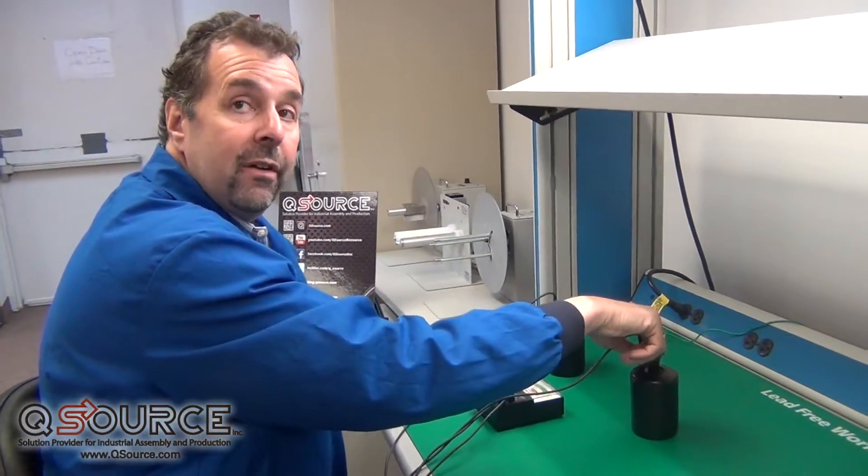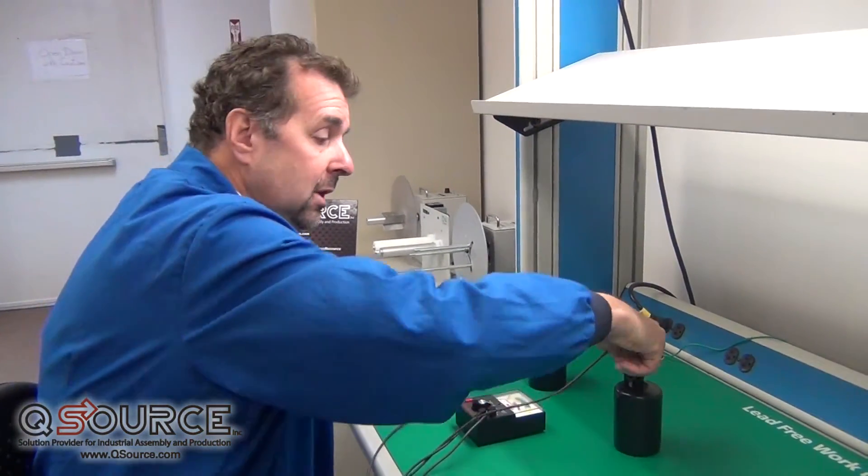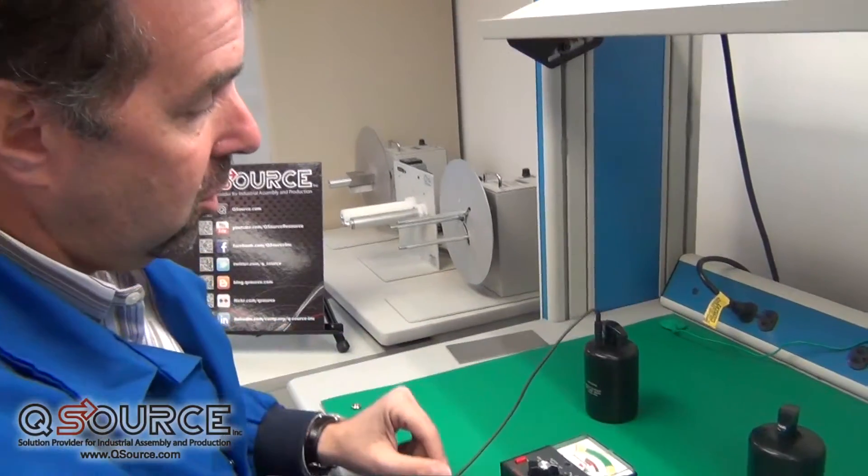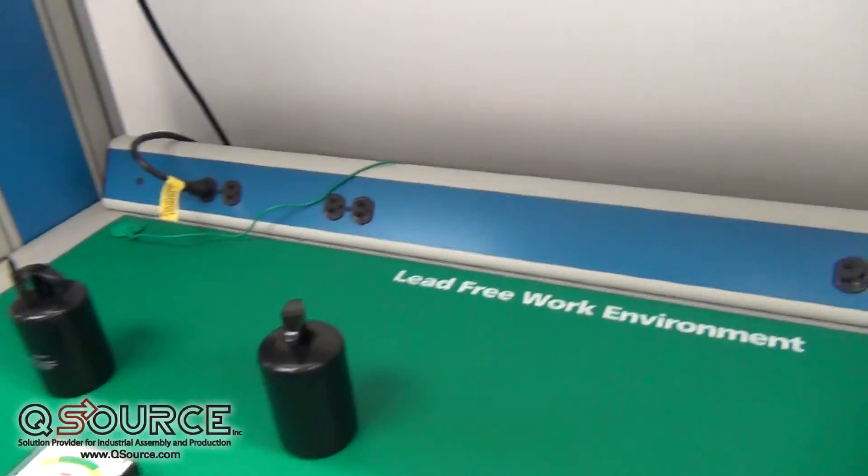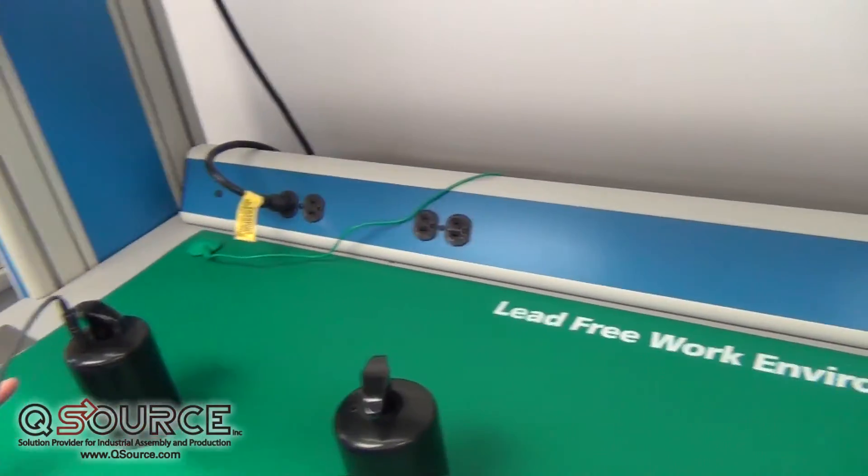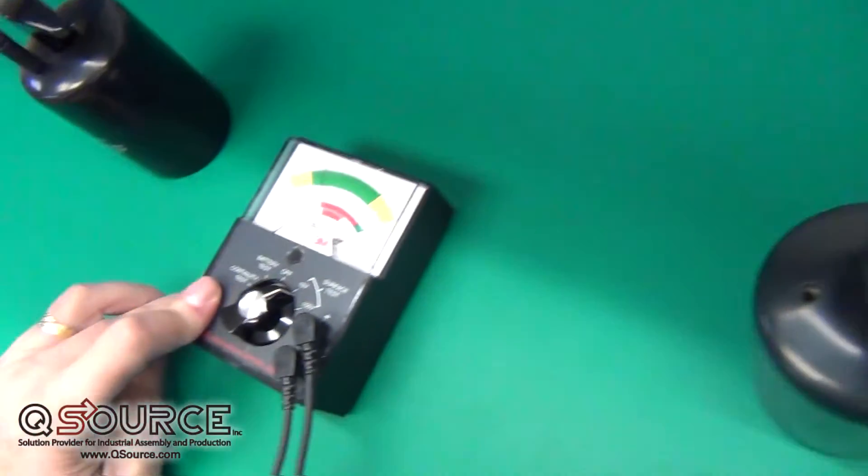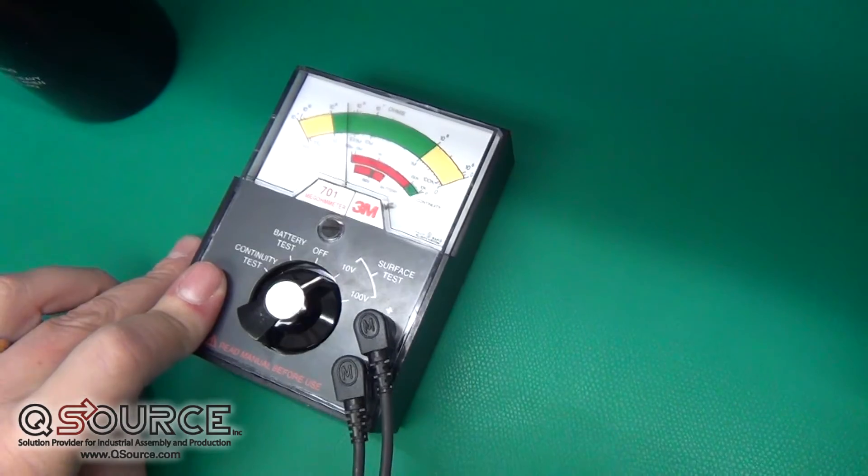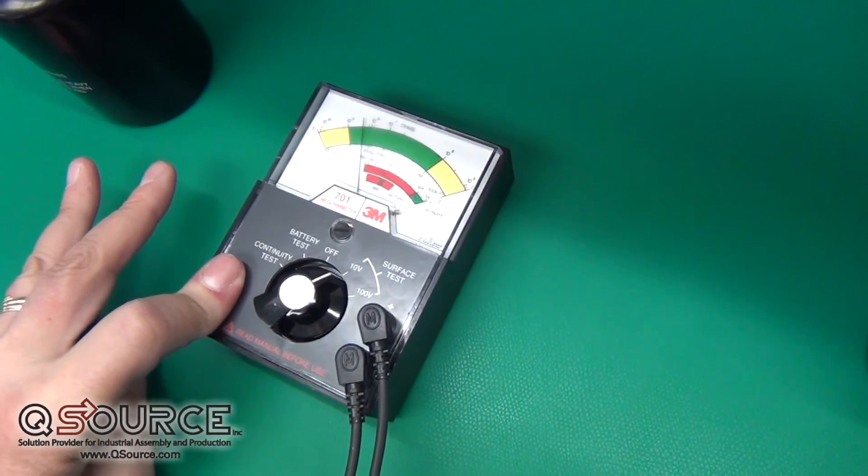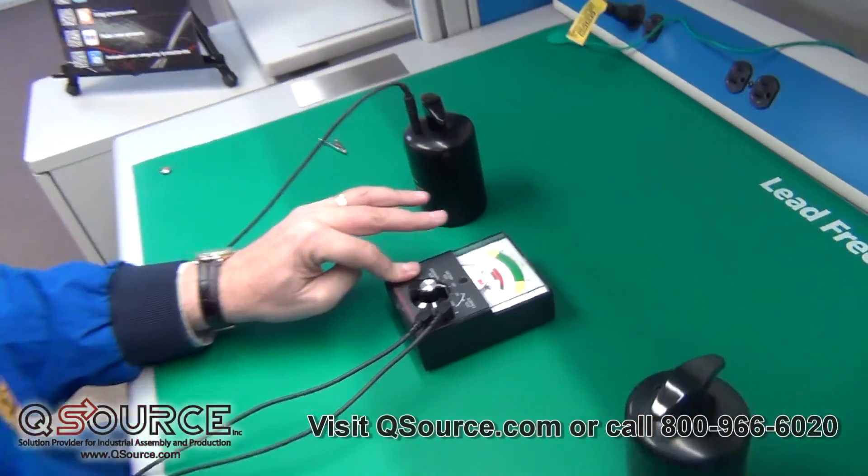The next part of this test is we want to verify that the mat is properly grounded. So we'll take one of the probes and put it into the ground of the electrical outlet, and we'll leave the other five-pound weight on the mat. We can see that any charge generated on the mat will go right to electrical ground at a static dissipative rate.